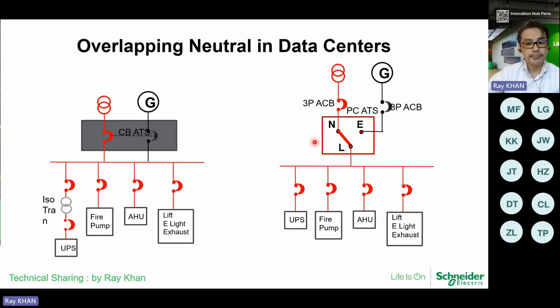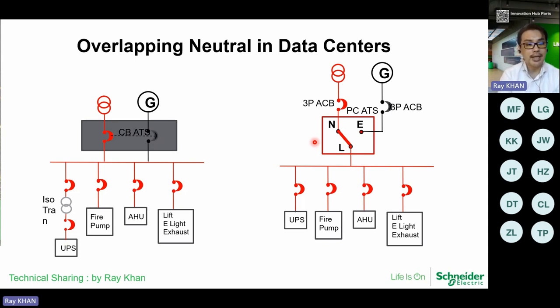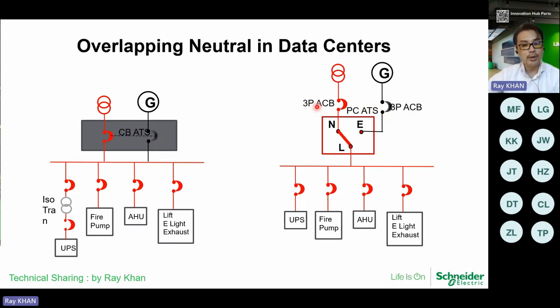For data centers using the ATS design, there is an isolating transformer just before the UPS that takes up significant space. By using overlapping neutral ATS, it eliminates the need for an isolating transformer. Regarding three-pole versus four-pole incoming: for three-pole circuit breakers, if there's a fault, you clear L1, L2, and L3, and the neutral is not broken. The recommendation for overlapping neutral applications is three poles, where the neutral remains intact.